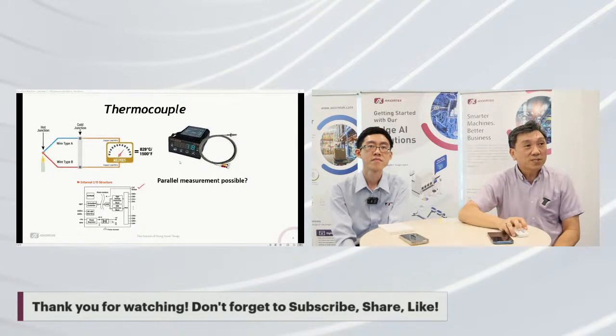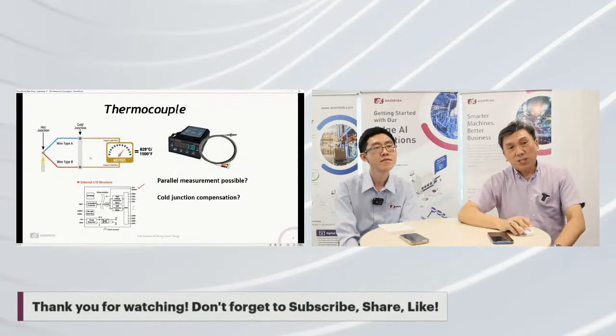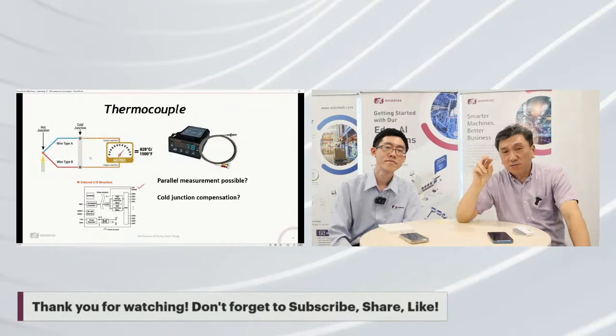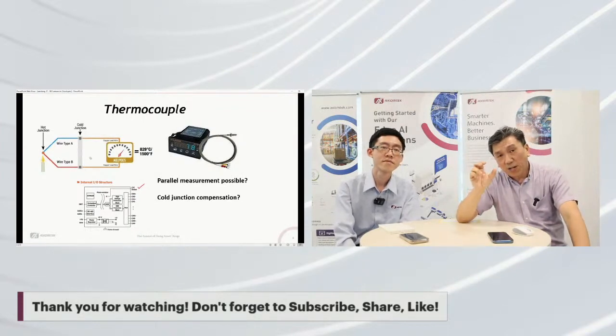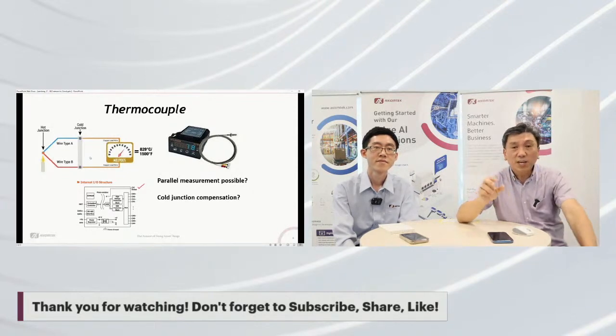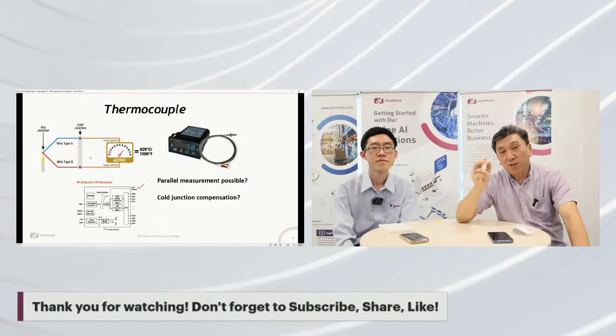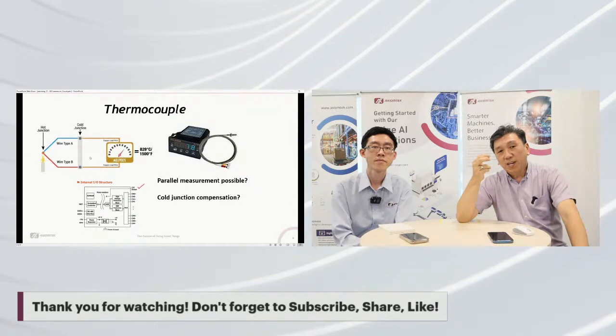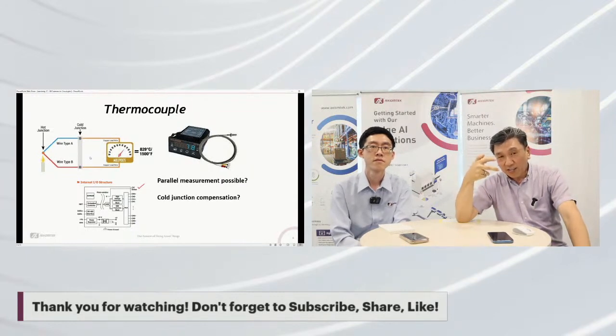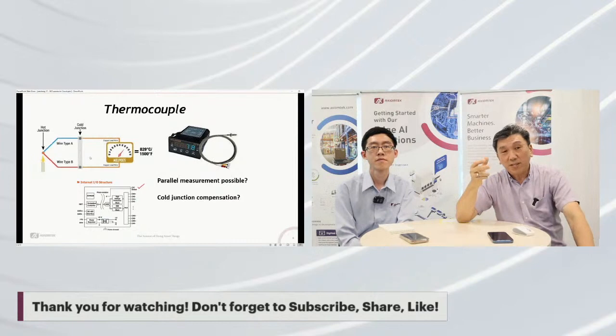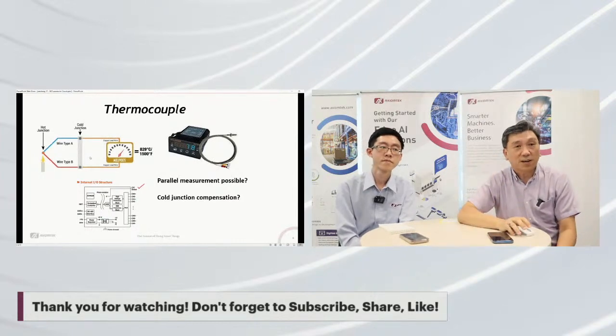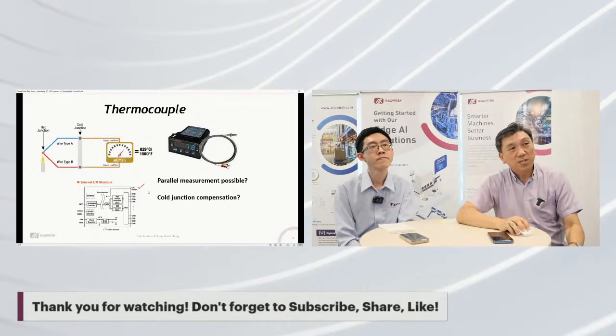So you have this kind of issue during what we call... there's one part in the thermocouple called cold junction compensation. Some of the modules we use already come with this cold junction temperature compensation. Cold junction temperature compensation is basically offsetting the voltage drop across the thing, because in thermocouple measurement, you actually need 0 degrees at the connection point. So cold junction compensation helps you compensate for that, and then you get an accurate reading. This is one part of the measurement in terms of thermocouple.